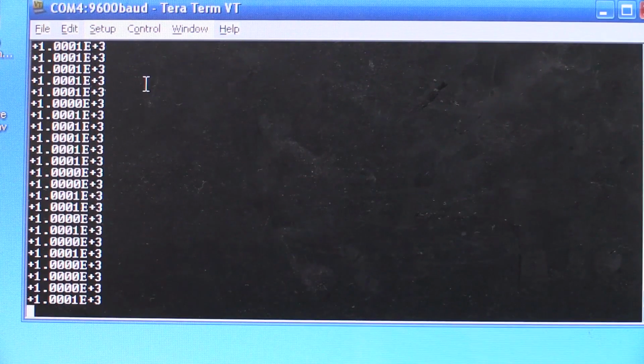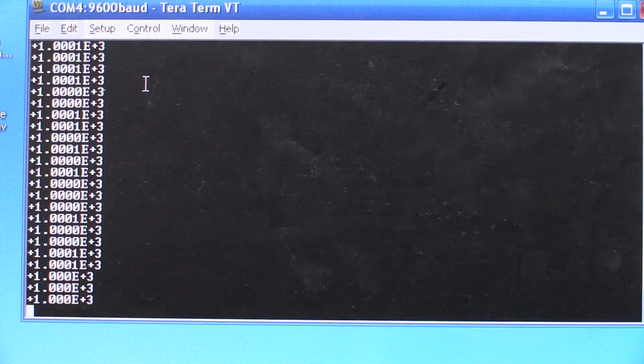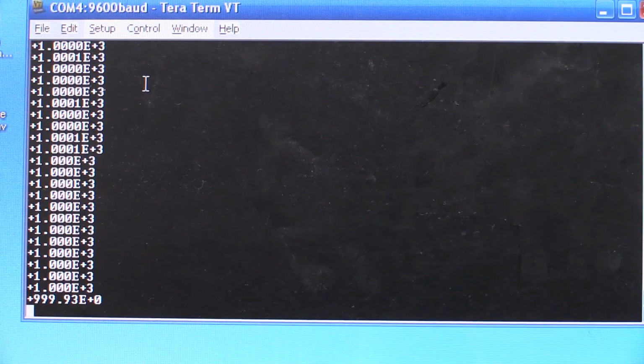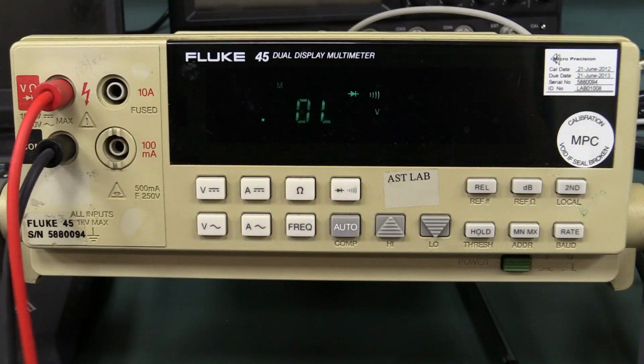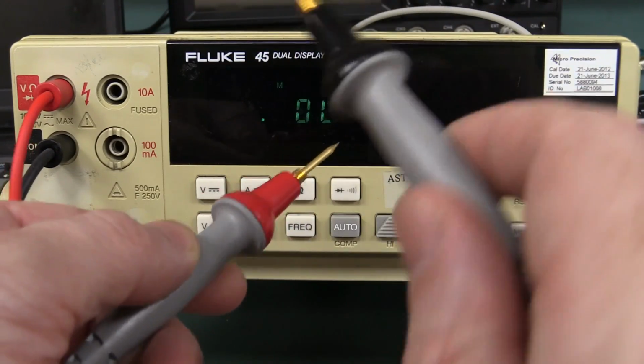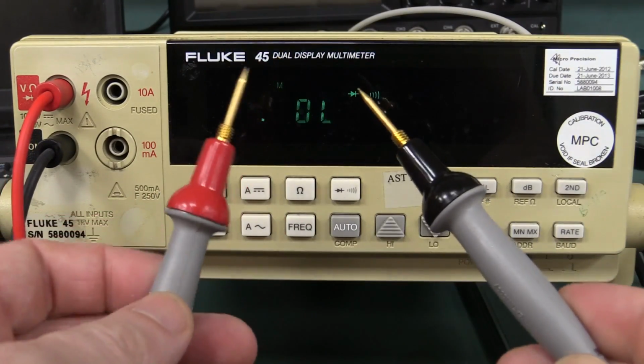So if I set that print mode to 10, then as you can see, it's happening like once per second or whatever now. But that will depend on the rate. So if I go to the faster mode, you can see it actually outputs, ticks over that data faster, and in slow mode it'll probably be 1, 2, 3, 4, 5. There we go, every 5 seconds, and we can set that to output data at whatever rate we like. And we'll try the continuity buzzer. Oh, that, folks, is as good as it gets.